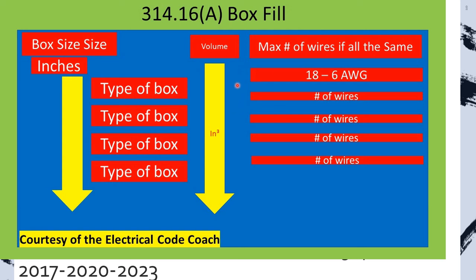That's all we're concerned with. We're not concerned with any metric designators inside of this table. We want to be dealing with cubic inches. And the reason it's cubic inches is because we have three different measurements. We have four by four by whatever the depth is. In this column, you're going to find the maximum that you're allowed to fill each box.